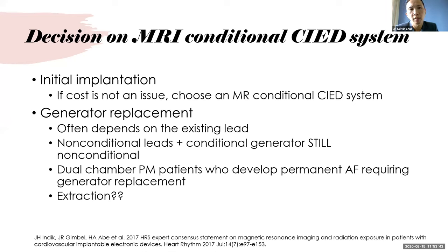And of course, the next decision often comes when the patient turns up for generator replacement. I personally rely on looking at the existing leads—if the existing leads are non-conditional, then even if you implant a conditional generator, the whole system is still considered MR non-conditional. But of course, some existing leads may gain MR conditional status, so that might be a consideration.